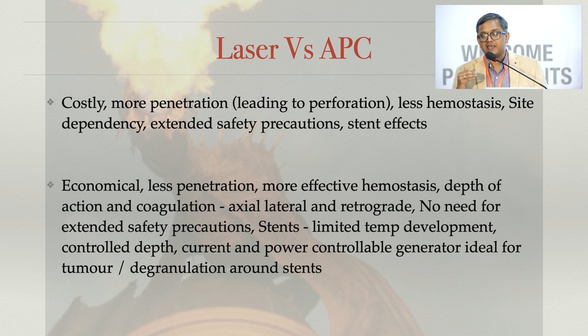But when you're doing it with APC, it's economical, lesser penetration, amazing for hemostasis. The depth and the effect is much more controllable with the power settings. The machine is much smaller and sleeker. There is no need for extended safety precautions, except the fact that your FiO2 should be less than 0.4. So that's the reason why, again, APC scores over laser as well.